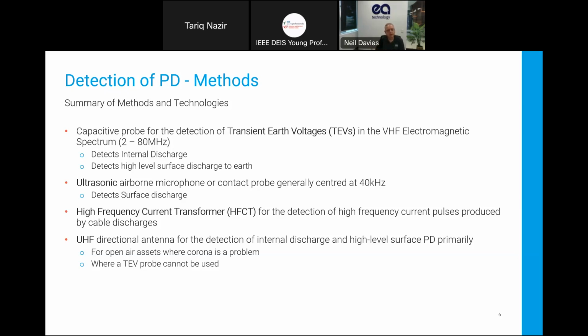So then we started back in the early 1990s introducing a complementary technique of ultrasonic alongside transient earth voltage to detect the problems that we were seeing on surface discharges. So ultrasonic, particularly airborne, if you've got an air passage from the outside to the inside, is the most sensitive. And then there's also contact probes that are used for detecting inside termination in sealed chambers.